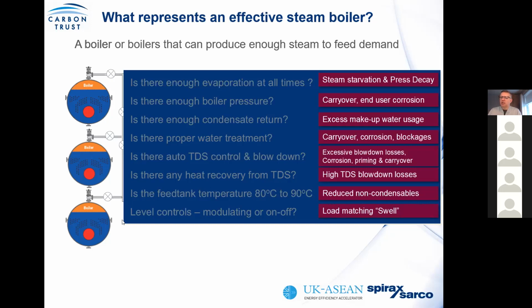And a swell is the term given to when there's a rapid depressurization of a boiler. And we're not saying from 10 bar to 2 bar, but you could see from 10 bar to maybe 9 bar or 9.2 bar. But that depressurization causes the water level in the boiler to rise significantly in a very short period of time. And in doing so, you end up dragging water into the steam system at a point in time where you have high steam demand.